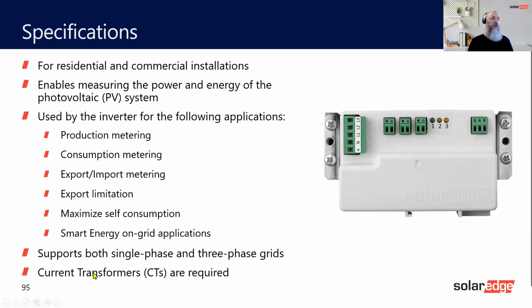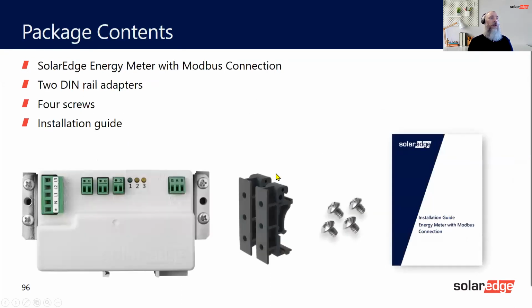Supports single and three-phase grids and has CTs. This here is the power, neutral, L1, L2, L3. And then we've got CT3 here. It does say underneath, so be careful you don't get confused. So CT3, CT2, CT1, and then 1, 2, and 3. These do not relate to this, so don't get confused. And then you've got Modbus connections on here. This is what you get in the packet. You get the meter, you get an instruction book, you get some screws, and you get the DIN rail mounting bracket here.